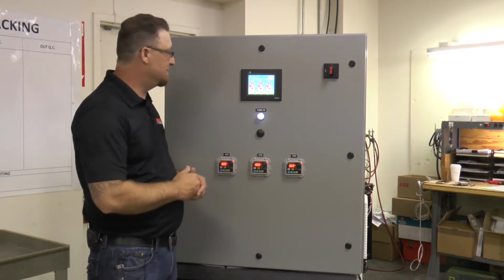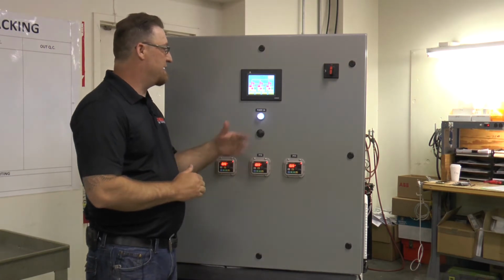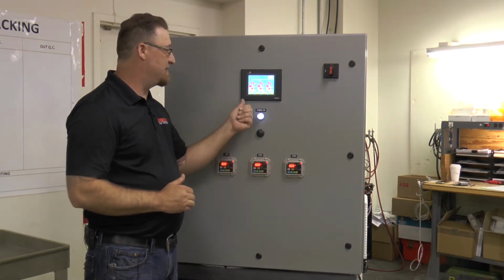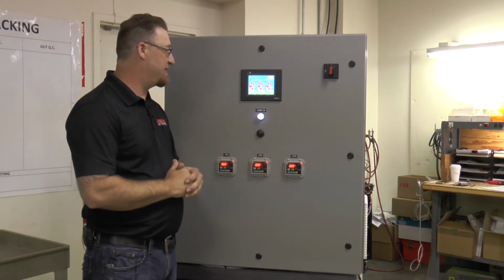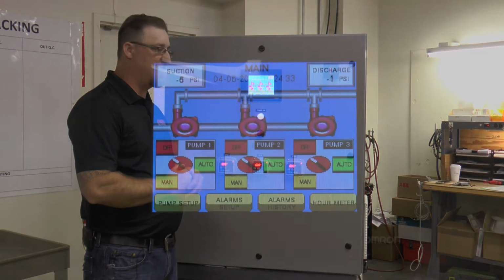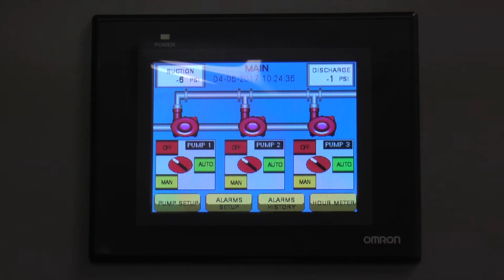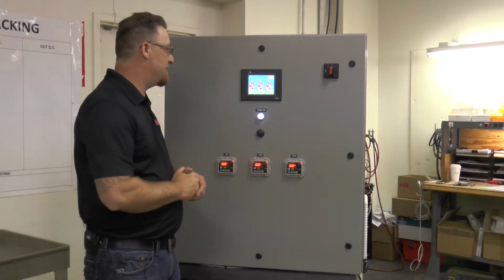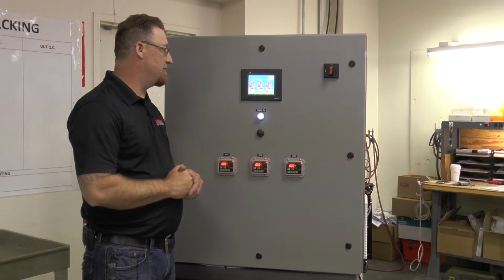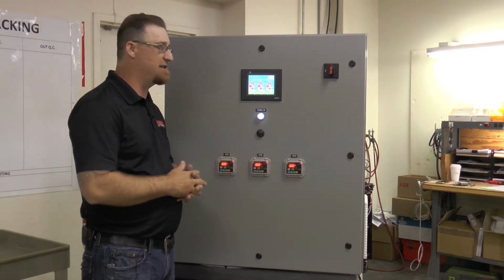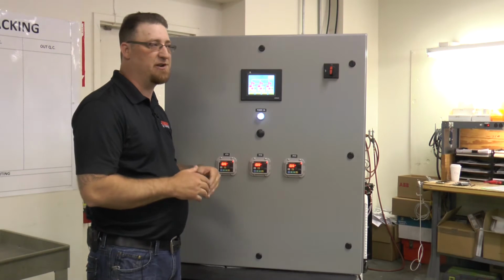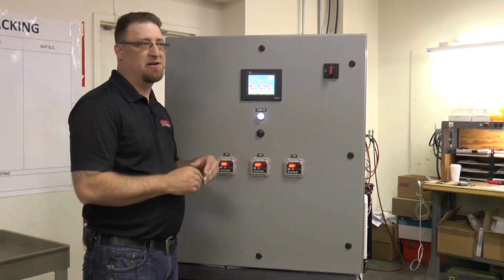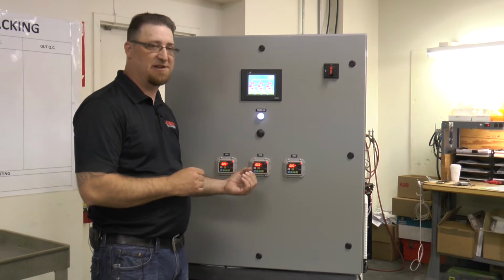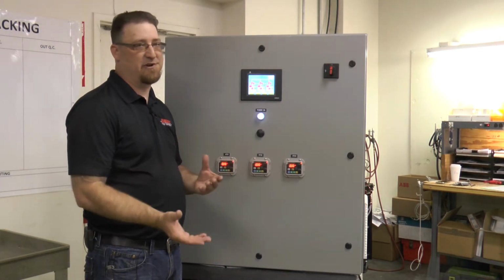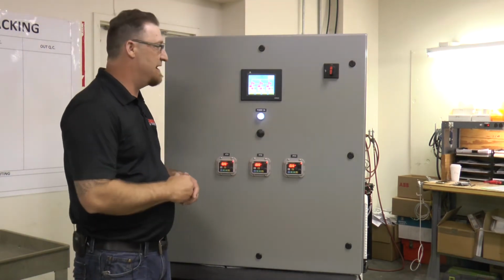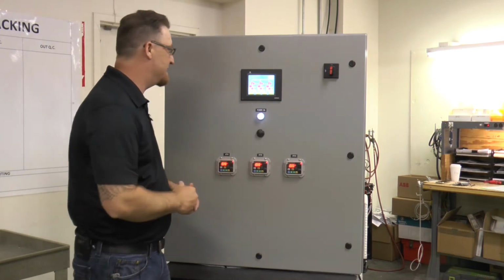So first off, you can see that there are buttons along the bottom of the HMI or the touchscreen, and they say pump setup, alarms history, and hour meter. So everything you need to know to set up your pumps, and when you want your pumps to come on, at which pressure, and when you want your pumps to turn off, at which pressure. And there's also on and off delays, and I'll go through that here in just a second.